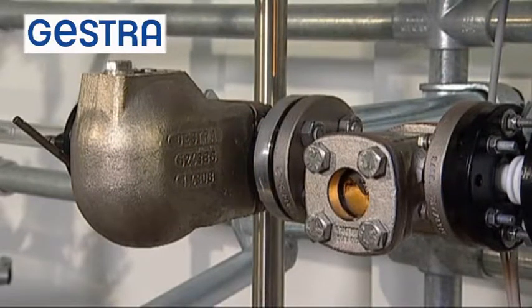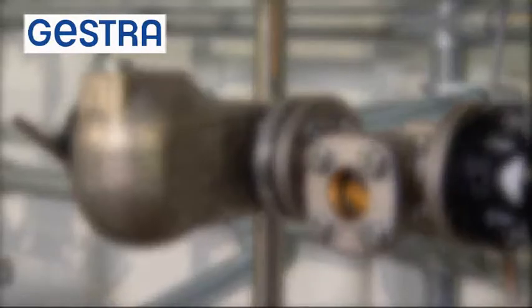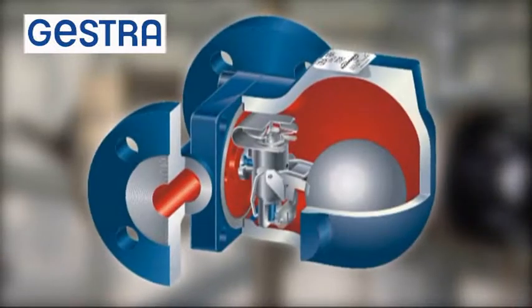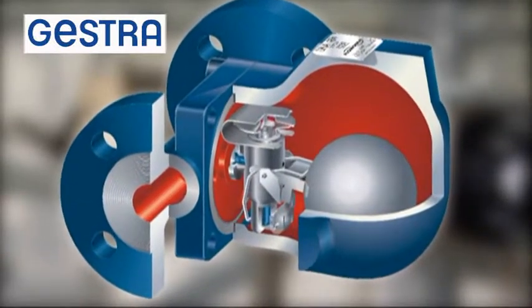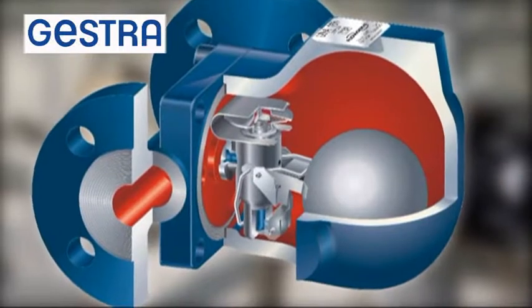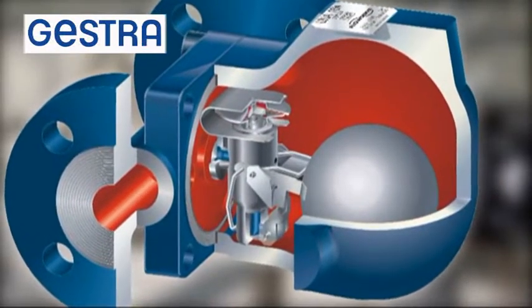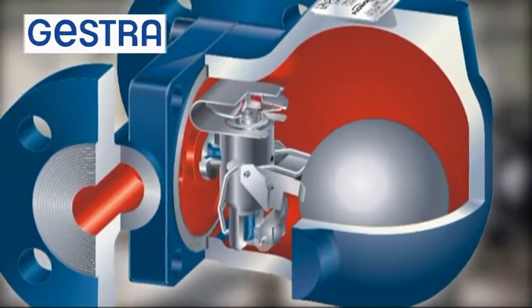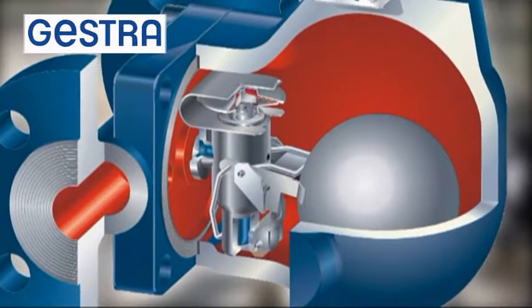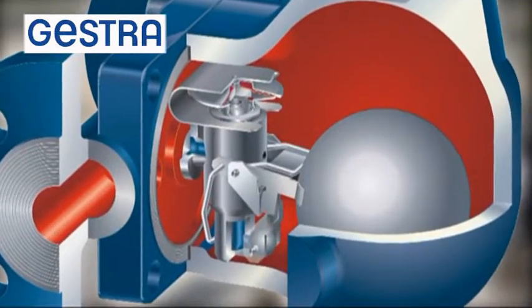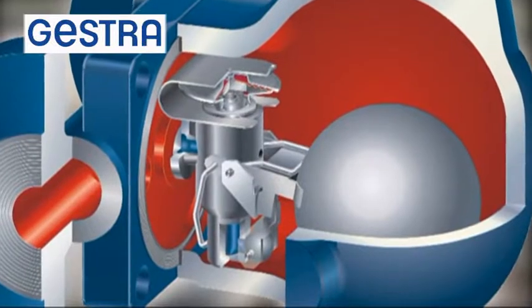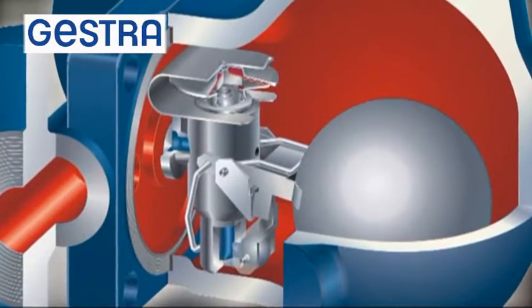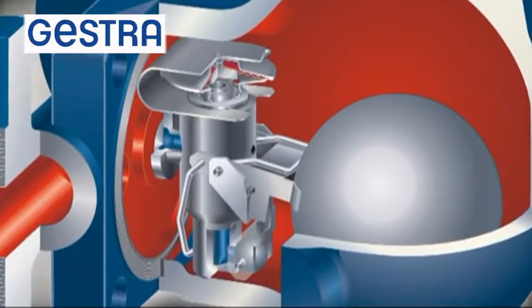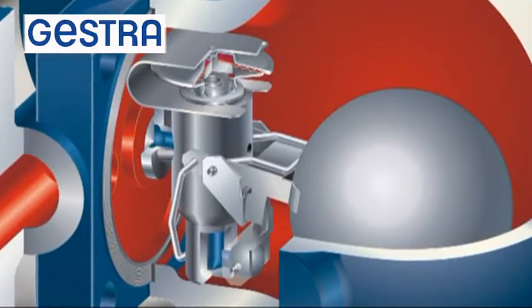GESTRA ball float traps have a regulator which functions by having a float pull a rolling ball off an orifice when condensate flows into the body. This opening is called the orifice and can have various diameters depending on the differential pressure. Through the differential pressure that is applied, the condensate is pressed through this small orifice and flows through the condensate line into the vessel located downstream.